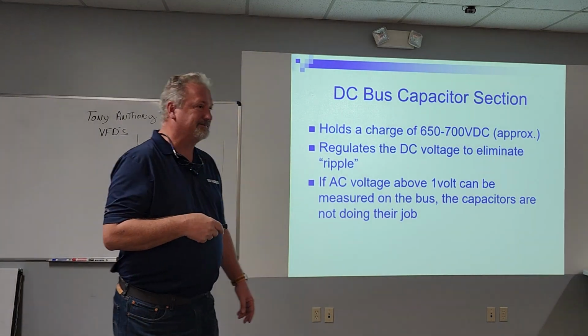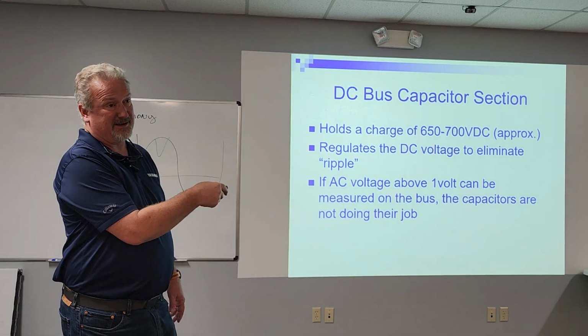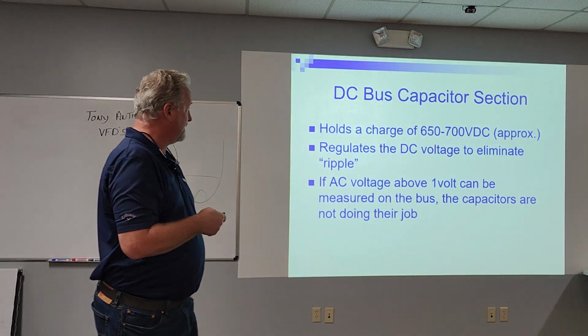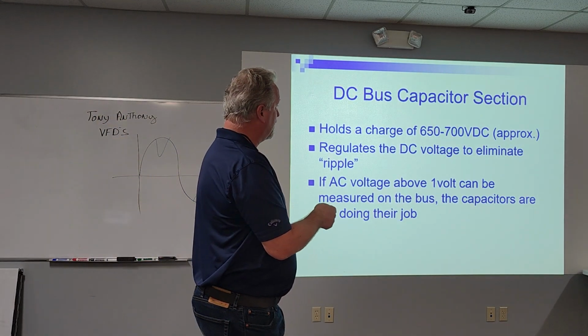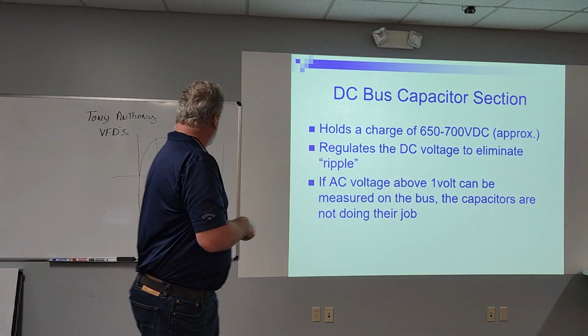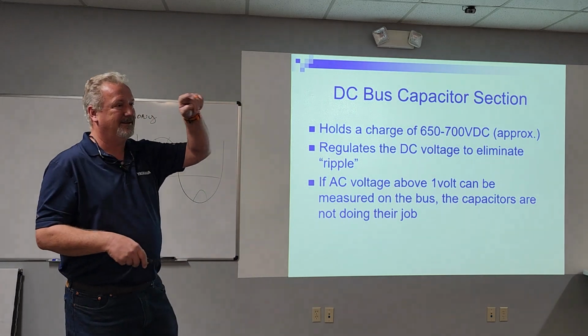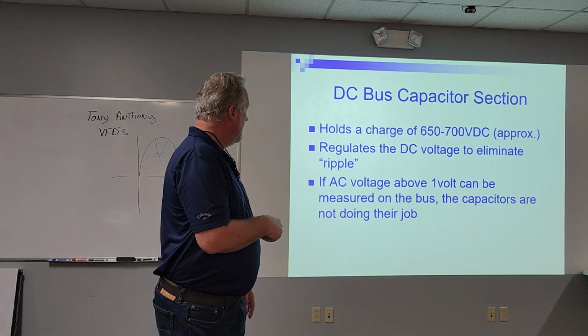So it should be about that. If it's a 230, it's going to be obviously a lot less than that, but this is for a 460. It regulates the DC bus voltage to eliminate ripple. Remember we talked about these little humps? It's going to fix that, and you'll see that here in a second.